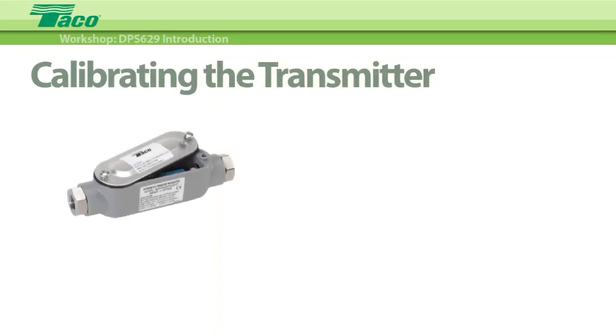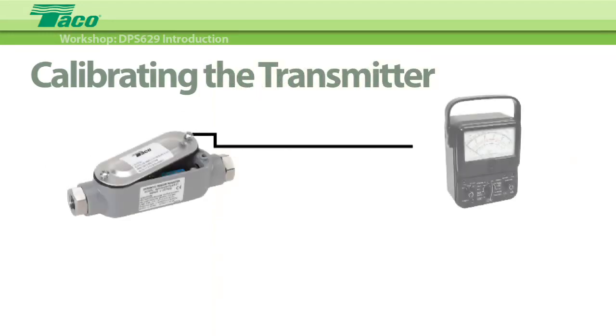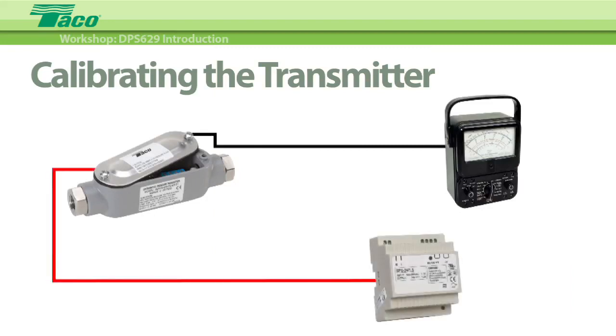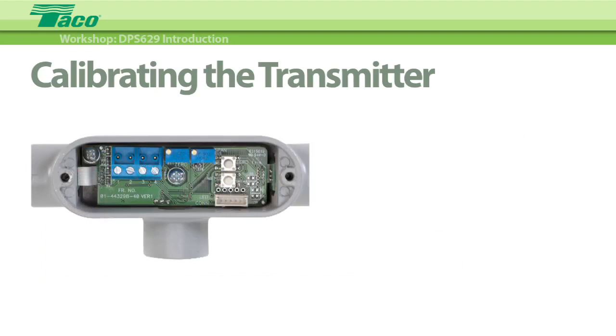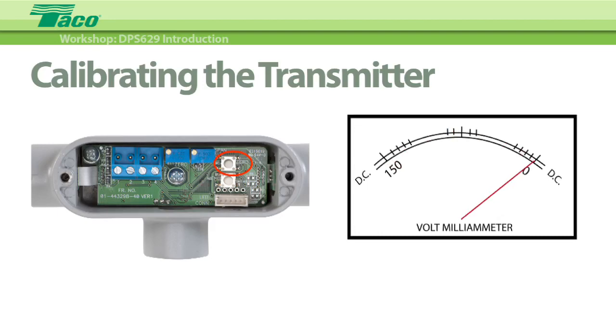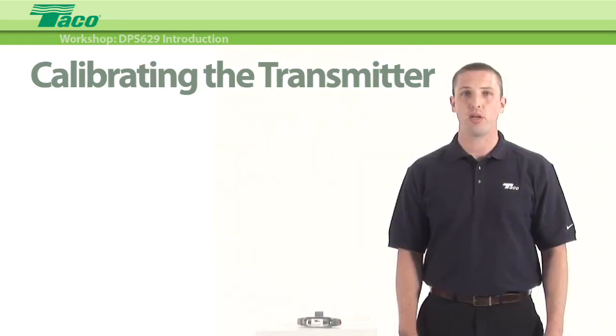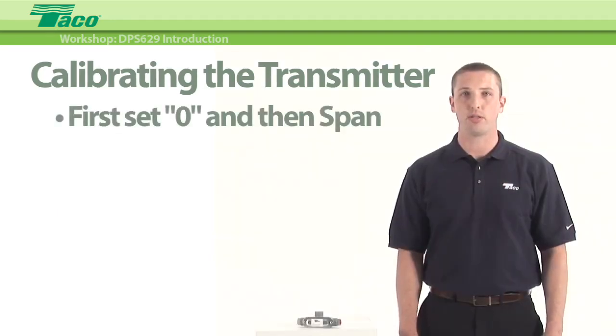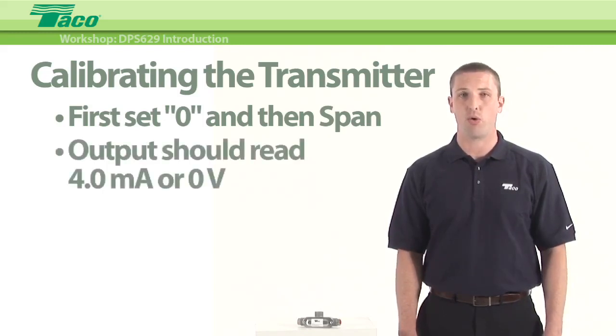Depending upon if it is a 2-wire or 3-wire system, connect the voltmeter or milliamp meter and power supply, being careful to observe polarities. Leaving the pressure ports vented, press and hold the 0 switch for about 4 to 5 seconds. The 0 point should now be set and if the display is present, the display will read 0. Calibrating pressure should begin with setting the 0 first, then the span, since the 0 set point will affect the span value. Once the 0 is set, your output reading should be close to 4 milliamps or 0 volts.